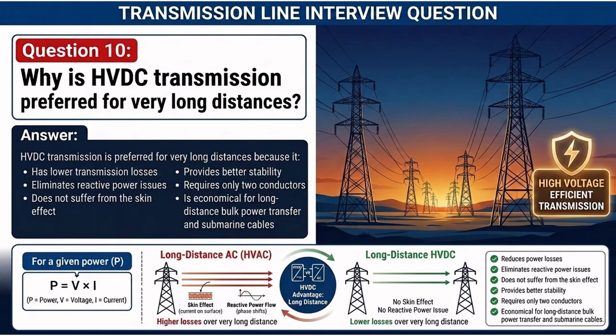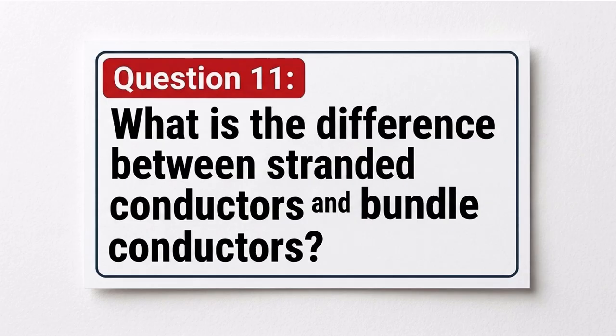Why is HVDC transmission preferred for very long distances? HVDC transmission is preferred for very long distances because it has lower transmission losses, eliminates reactive power issues, does not suffer from the skin effect, provides better stability, requires only two conductors, and is economical for long-distance bulk power transfer and submarine cables.